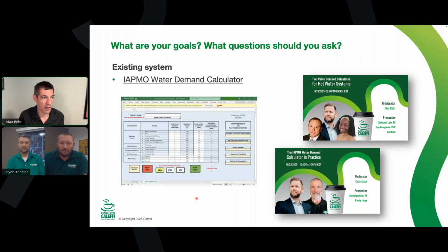If you got a phone call and said, hey, I just picked a thermostatic mixing valve, and I used the original 1940s Hunter's curve, and then you got another call at the same time and said, hey, I just sized a thermostatic mixing valve with the IAPMO water demand calculator, which one would you say is going to end up with a shorter phone call as far as troubleshooting goes?